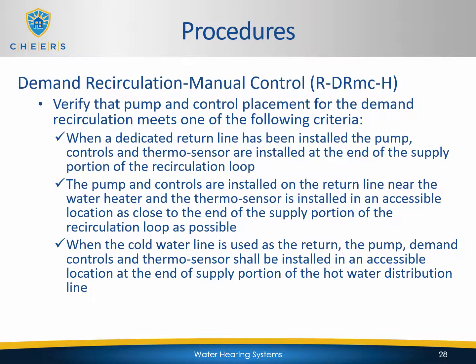You will need to verify that pump and control placement for the demand recirculation system meets one of the following criteria. When a dedicated return line has been installed, the pump, controls, and thermosensor are installed at the end of the supply portion of the recirculating loop, or the pump and controls are installed on the return line near the water heater, and the thermosensor is installed in an accessible location as close to the end of the supply portion of the recirculation loop as possible. Or last, when the cold water line is used as the return, the pump, demand controls, and thermosensor shall be installed in an accessible location at the end of the supply portion of the hot water distribution line.